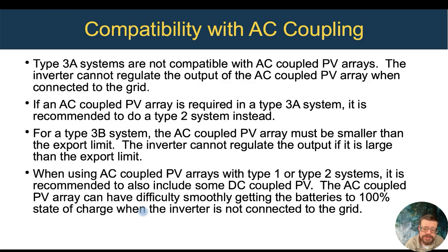But in my experience, usually getting those batteries higher than 95% is kind of tricky. It depends on the particular loads you've got and how that relates. But often you're going to have to set your stop value for your AC coupled PV array at 95% when you're off grid in order to prevent some system instability. What that means is that if you don't also have some DC coupled PV array, you're not going to be able to do that last little 5% of charging and get it up to 100%.